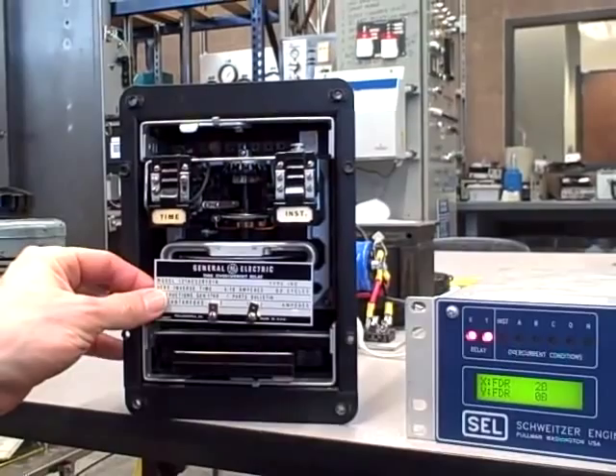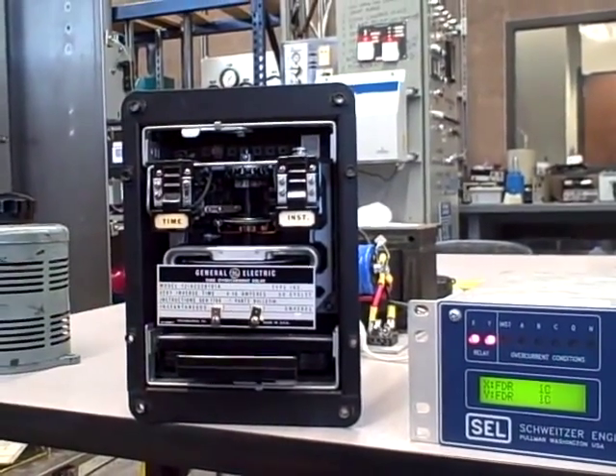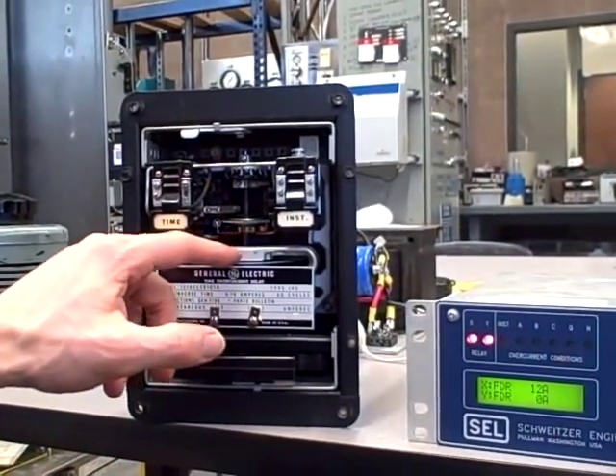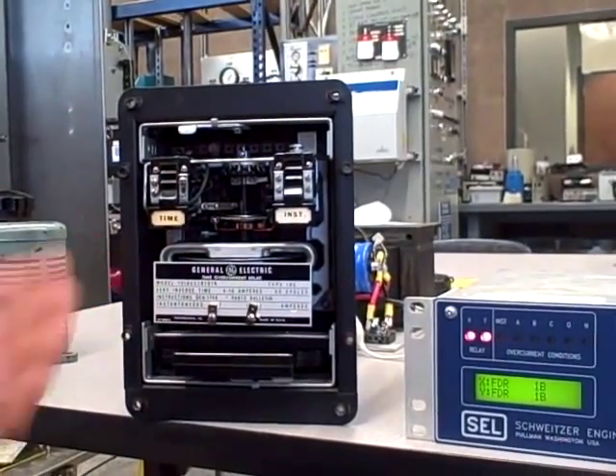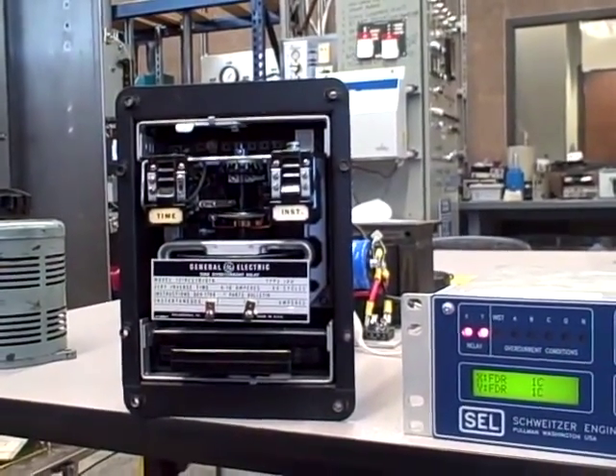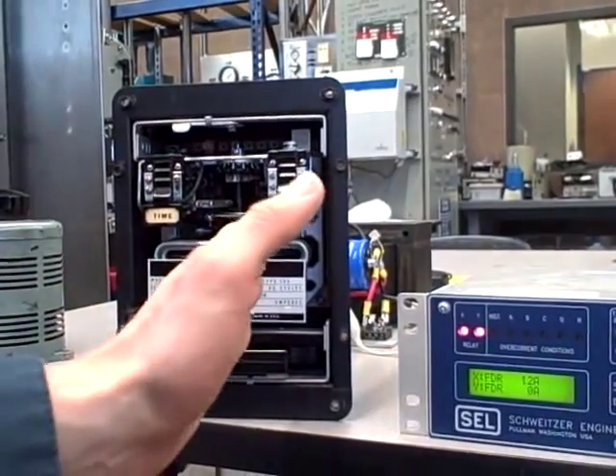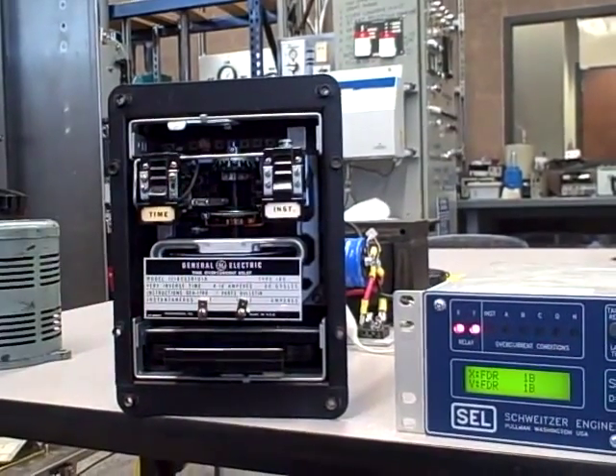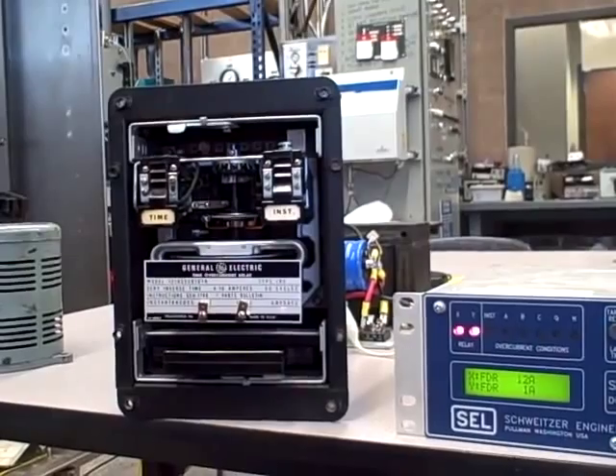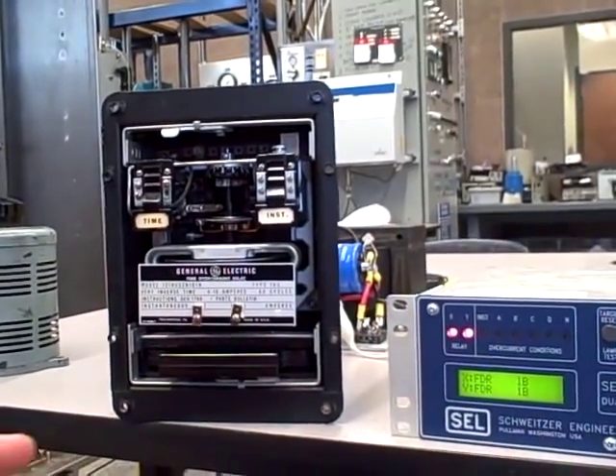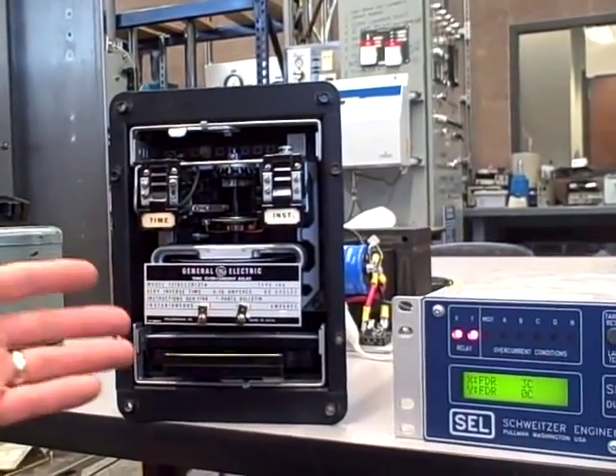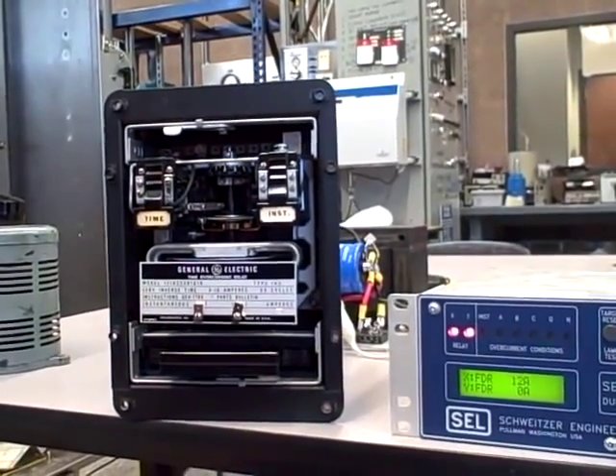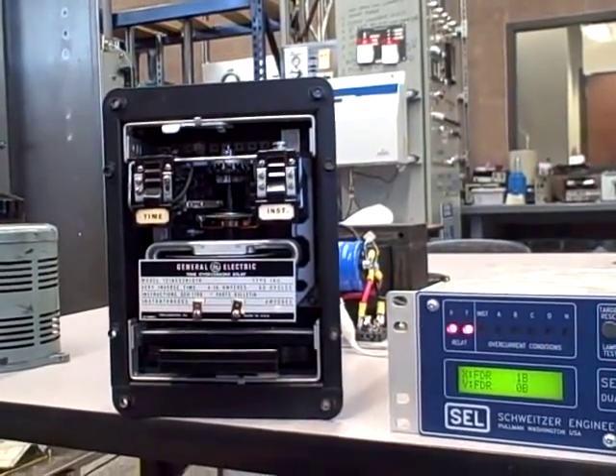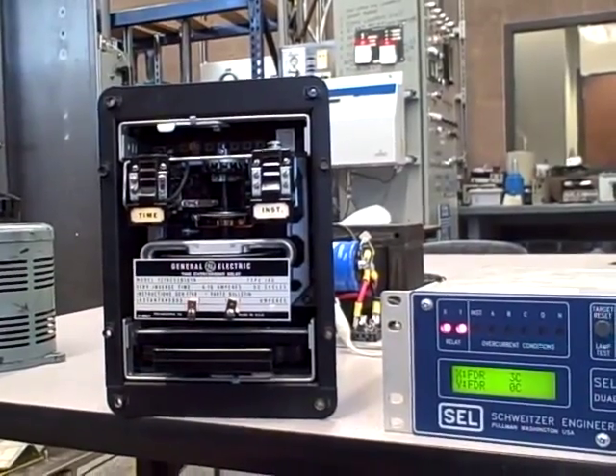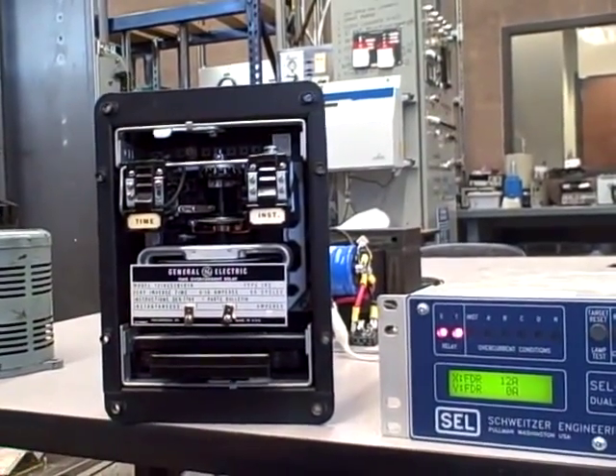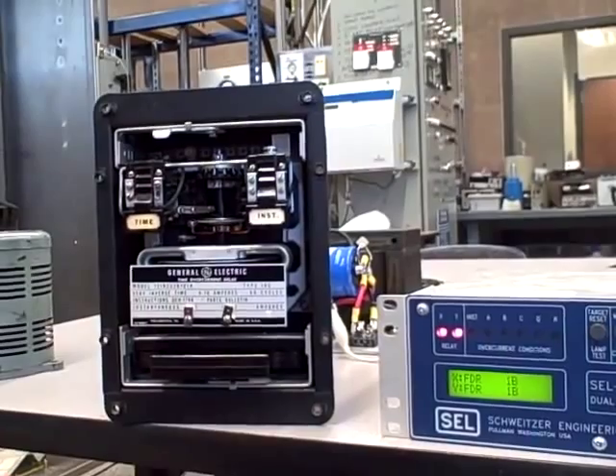Actually, other companies other than GE made them, but the electromechanical style used an induction disc that would spin as you applied an overcurrent condition beyond the pickup value. And that disc, as it would spin, would take time before it closed the trip contact for the breaker. So that would give the overcurrent condition a certain amount of time to persist before we actually cut the power off. That's useful for things like inrush current on motors or for thermal constraints on devices like transformers that can take a certain degree of overcurrent before they actually run into any trouble.